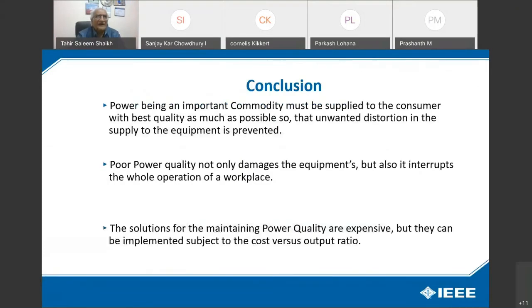Now I come to the conclusion. Power, being an important commodity, must be supplied to the consumer with the best quality possible so that unwanted distortion in the supply to the equipment is prevented. Poor power quality not only damages the equipment but also interrupts the whole operation of the workplace. The solutions for maintaining power quality are expensive, but they can be implemented subject to the cost versus output ratio. In the textile sector, product quality is disturbed. So there are so many things.